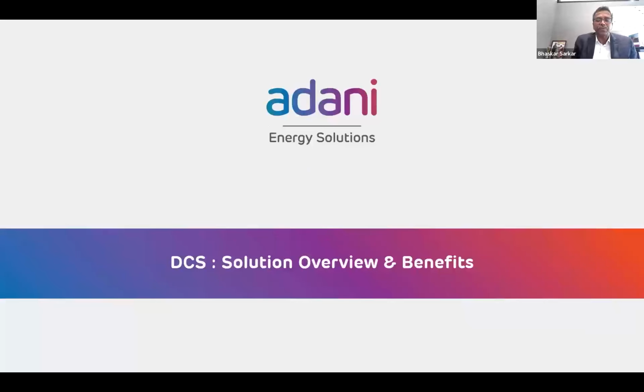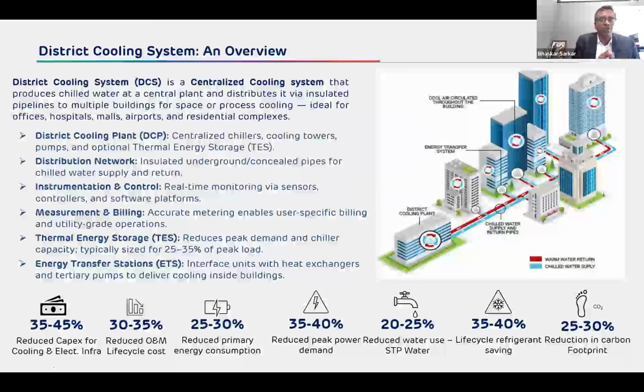So now I will take up a brief DCS solution overview. All of us know, but just to touch upon the points, the district cooling is a centralized plant. By definition, it is a separate plant in itself, which generates chilled water at 5 to 7 degrees. And the chilled water is provided through insulated pipelines to each and every building which is there in the vicinity of the network of that DCS plant. And again, it goes into the buildings, then it goes inside the shafts and corridors and flats or the commercial or industrial units, and it captures the heat and comes back at about 12 to 14 degrees back to the DCS, which is again cooled and again recirculated. So that is in brief the operation of the district cooling plant.